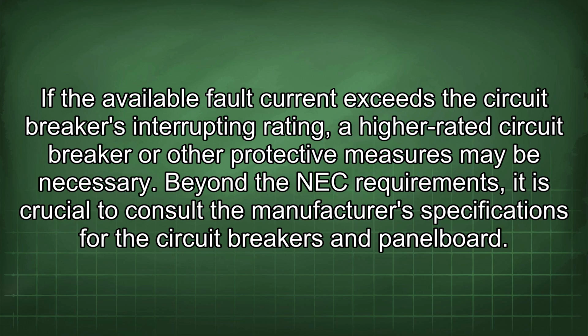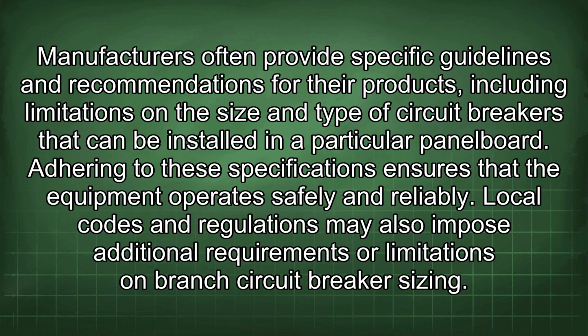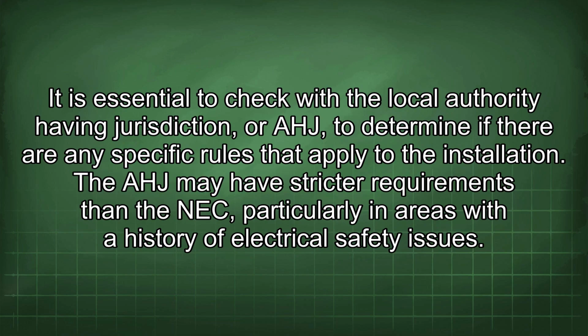Beyond the NEC requirements, it is crucial to consult the manufacturer's specifications for the circuit breakers and panel board. Manufacturers often provide specific guidelines and recommendations for their products, including limitations on the size and type of circuit breakers that can be installed in a particular panel board. Adhering to these specifications ensures that the equipment operates safely and reliably. Local codes and regulations may also impose additional requirements or limitations on branch circuit breaker sizing. It is essential to check with the local authority having jurisdiction, or AHJ, to determine if there are any specific rules that apply to the installation.